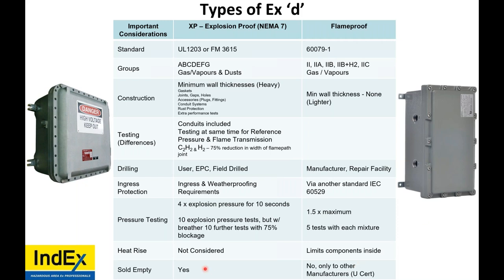Now, can you sell an empty enclosure? Can you receive an empty enclosure as an EPC? Well, for explosion-proof, you can. For flameproof, you cannot, only if you're a manufacturer, where you're planning on putting your own devices in there and then having the box independently certified.